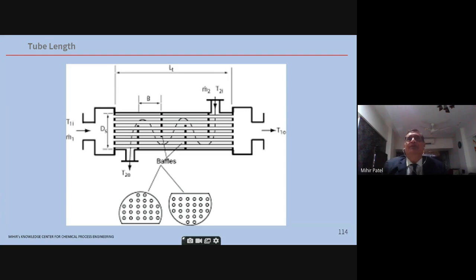Then your tube bundle removal in shell and tube types. The layout may dictate tube length also. So normally when you have a bundle removal, the piping person plans a vacant space where the bundle has to be removed. So if you have a very long tube length, you have to keep a very large space for the tube bundle removal. So that's why there also you have to compromise a little bit. Smaller tube length, less space kept for tube bundle removal. The process engineer has to interact for this while they are doing the thermal design.